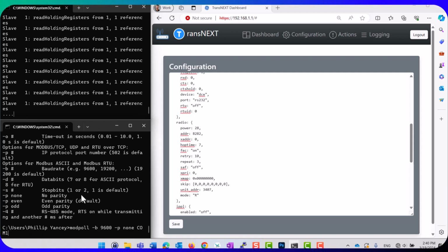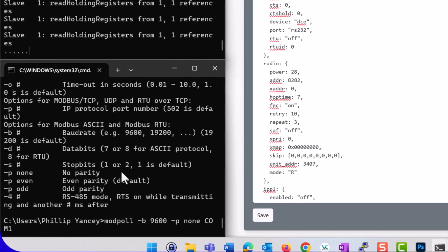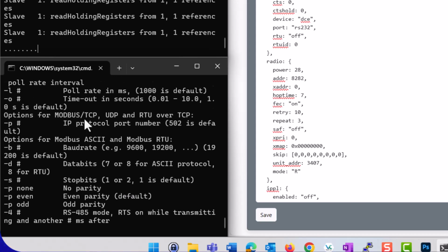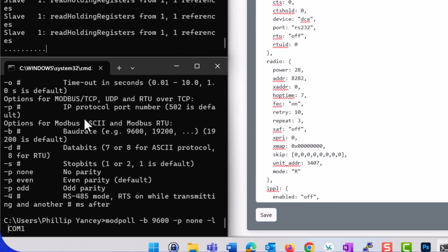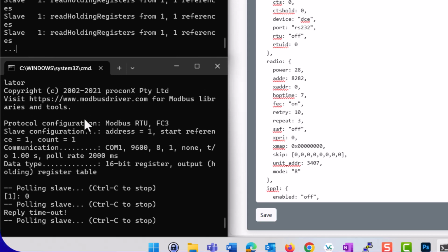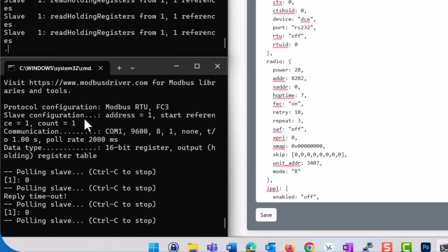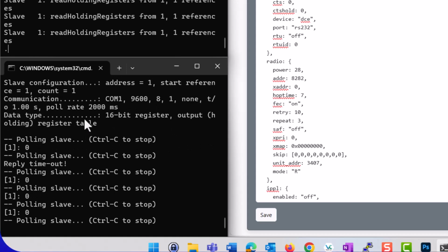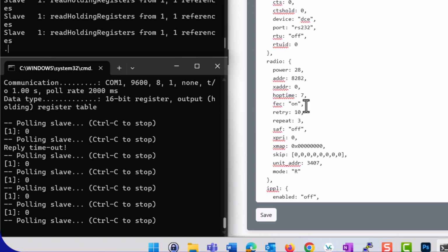I always like to see if I can make similar adjustments through the radio rather than through the polling. So if I put a timeout, let's see, poll rate, maybe if I change it from 1,000 milliseconds to 2,000, it'll probably be a lot cleaner. Nope, not at all. We still have a couple of missed polls, even with this slower rate. So the power is lower.